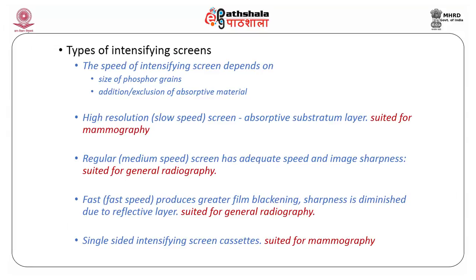The various types of intensifying screen depend on the size of the phosphor grain and the addition or exclusion of absorptive material. High-resolution, slow-speed intensifying screens with absorptive substratum are used for mammography. For regular medium speed, there is adequate speed and image sharpness well suited for routine radiography. Fast speed produces greater blackening of the film but sharpness is slightly diminished due to the reflective layer, though it is still suited for general radiography. Single-sided intensifying screens are well suited for mammography where better image resolution is needed.